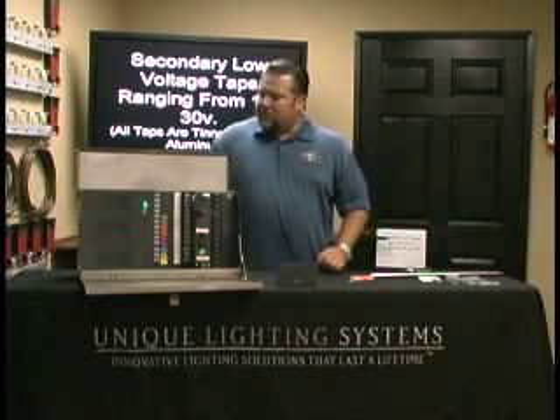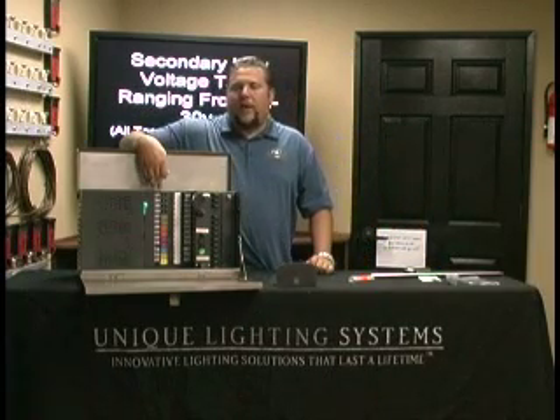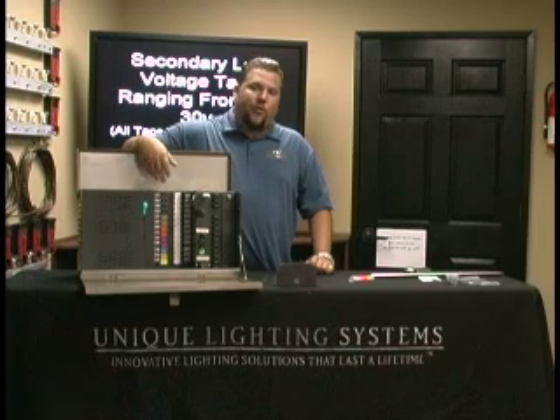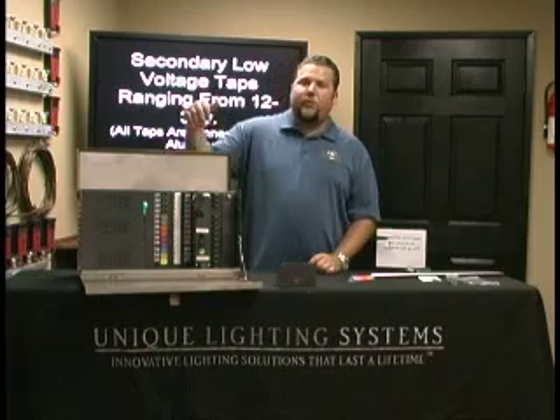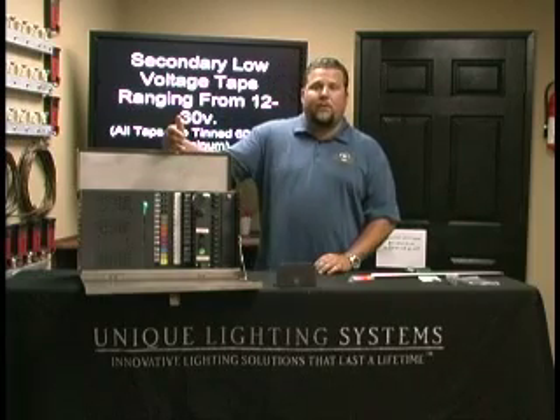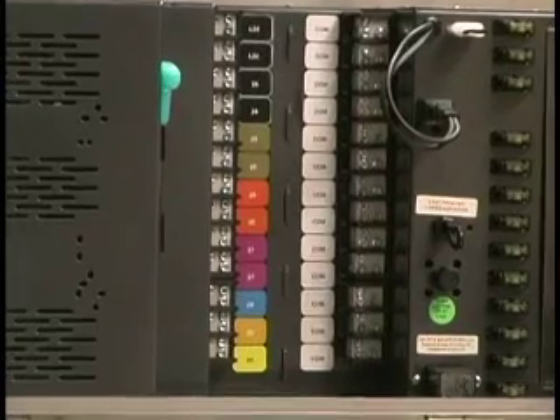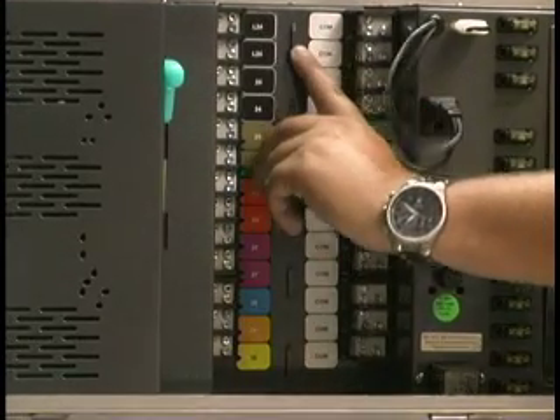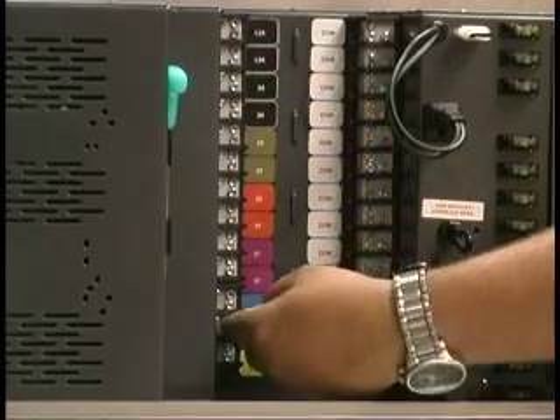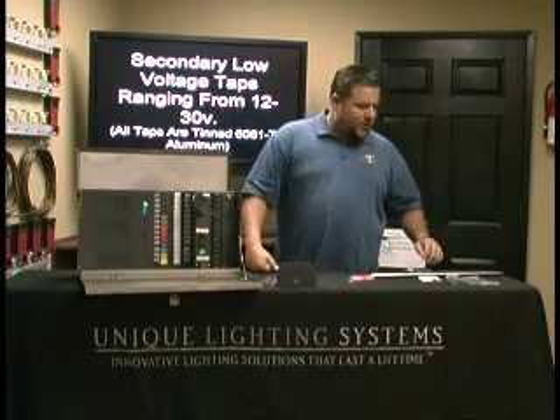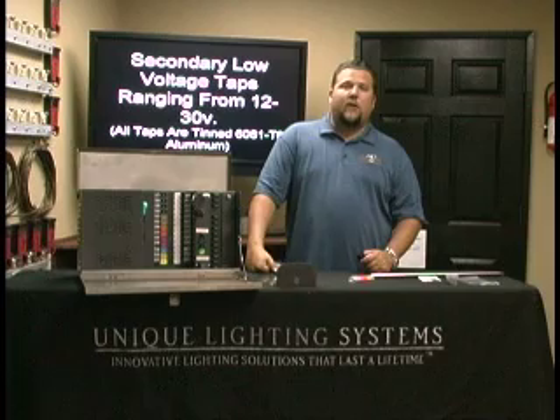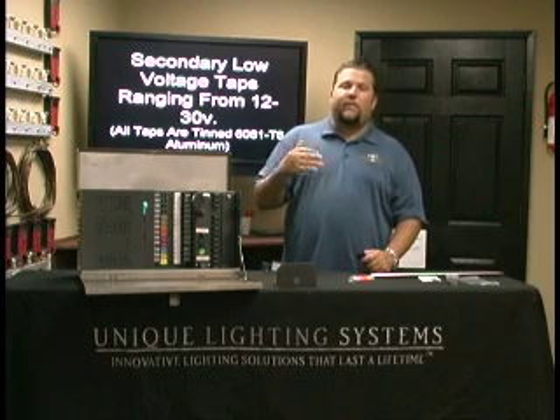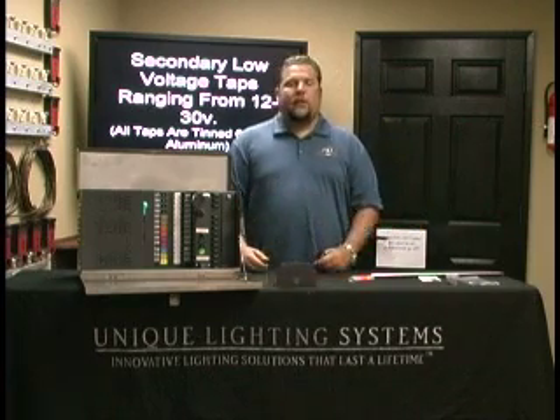The transformer's secondary voltage taps range anywhere from 12 to 30 volts depending on the voltage unit you buy. If you buy a 12 volt unit, you'll have 12 through 22 without skipping any voltages. In a 24 volt application, you'll have anywhere from a low 24 or 23 volt all the way through to a 30 volt tap. That makes things really nice, so you don't have to worry about skipping any voltages or balancing accordingly.